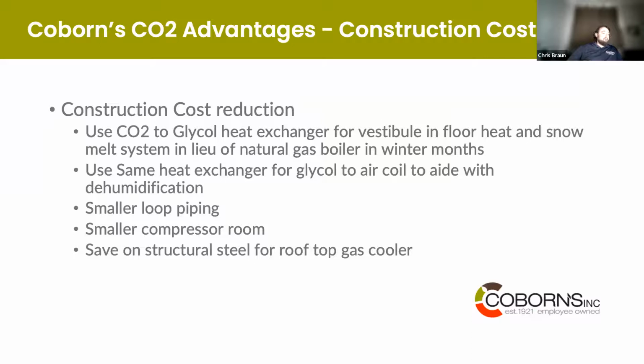As Doug alluded to, it's smaller loop piping. The system architecture is considerably smaller than a standard HFC system, so we've been able to reduce the size of our mechanical rooms or keep them the same size and add additional aspects to that mechanical room that don't take up space in other parts of the store. And then with only having one rooftop gas cooler, we don't have to spend money on structural steel for 2 or 3, 10, 12, 14 fan condensers like we have in the past with HFC systems. So that architecture and raw material costs have been going down just due to the sheer smaller size of a CO2 system versus multiple HFC systems. That's really interesting.